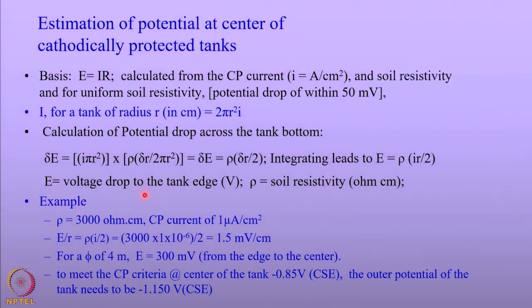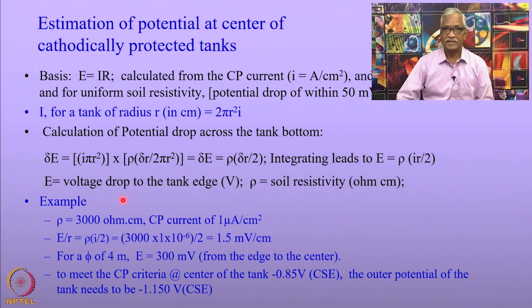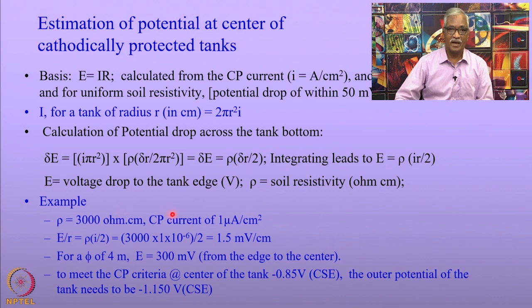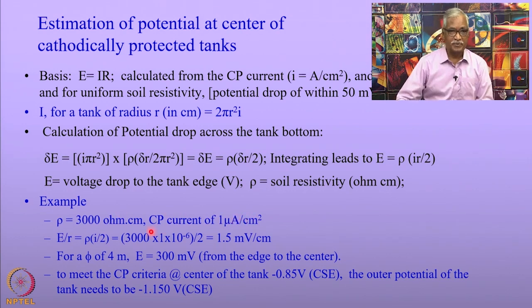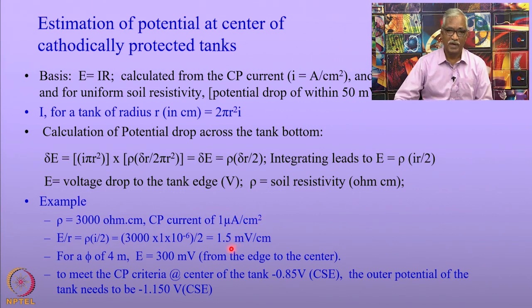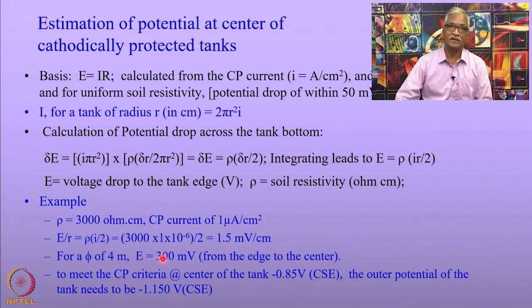To illustrate this, consider a case where the soil resistivity is 3000 ohm-centimeter and the current required for cathodic protection is 1 microampere per centimeter square. Substituting these values in the equation, the potential drop across 1 centimeter turns out to be 1.5 millivolt. For a tank of 4 meter diameter, the voltage drop from the edge to the center turns out to be 300 millivolt.